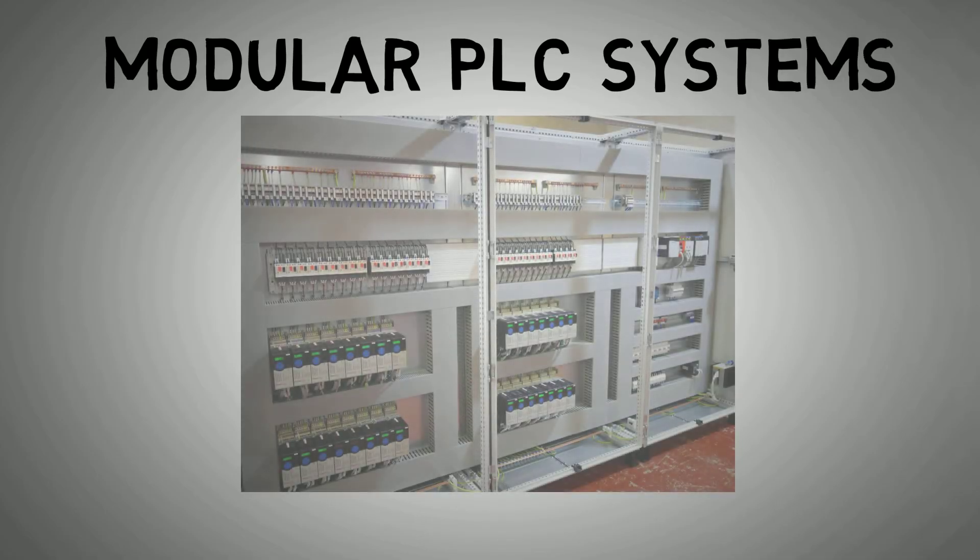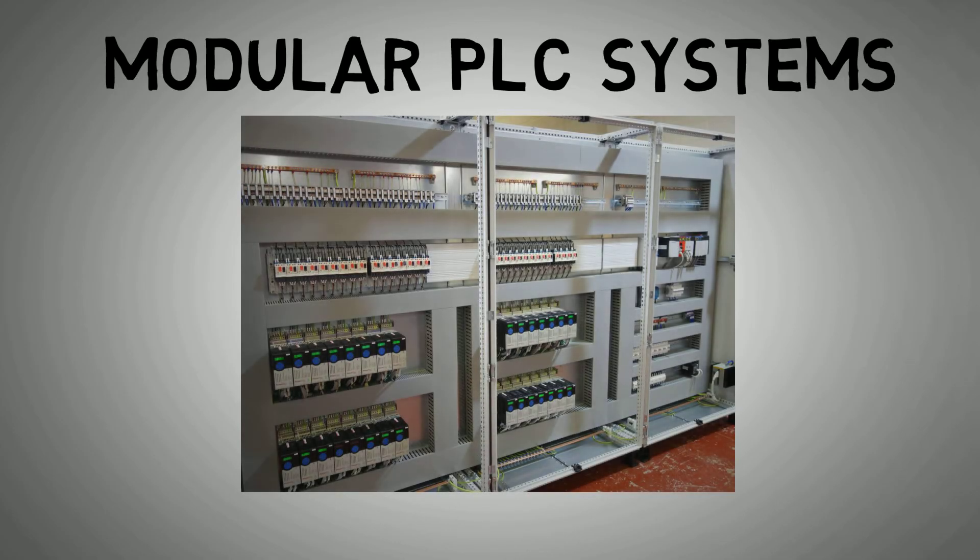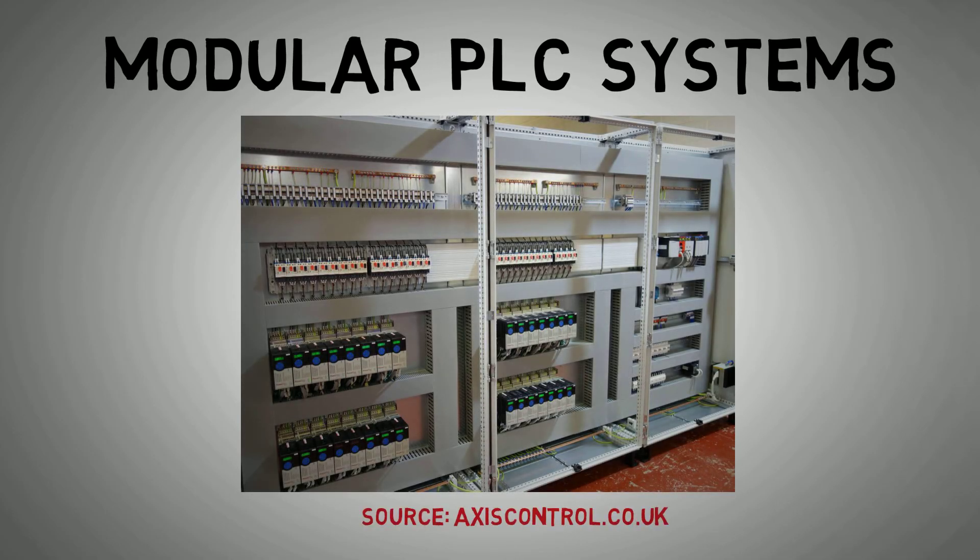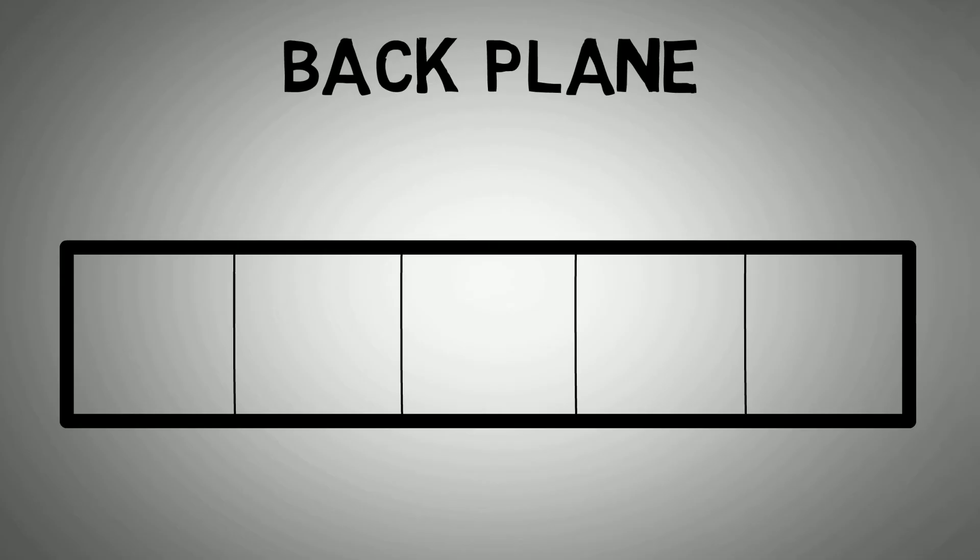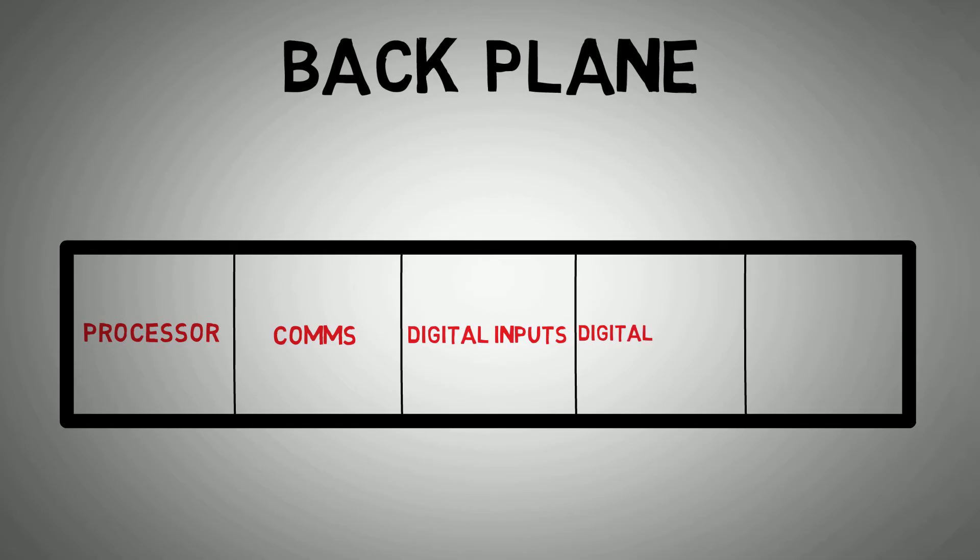In more complex systems, PLCs are usually mounted within their own control cabinets. For these customizable systems, you will often have a backplane that allows a modular approach to system design. The backplanes will be able to accept the processor and then any other modules that will be required for the system, such as comms cards and I.O. devices. Systems are usually specified with enough spare I.O. for further and future expansion.